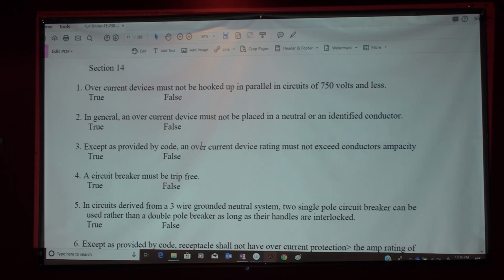Okay. Next question for next person. In general, an overcurrent device must not be placed in a neutral or identified wire. True. We discussed this yesterday. It shows more clearly on table 25. But the way I explained to you yesterday, you always put a fuse on the phase, never on the neutral. Just remember that concept. You never put a breaker or a fuse on the neutral, ever. Okay? Next person. Except as provided by a code, an overcurrent device rating must not exceed conductor ampacity. True. Perfect.